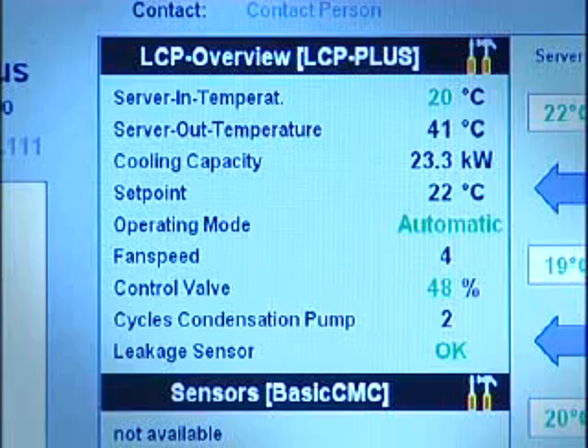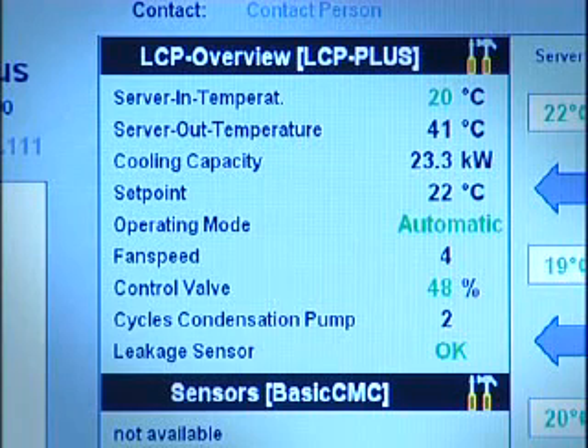Because of the large cooling capacity of the LCP Plus, it can be shared across a number of enclosures, effectively providing 2 enclosures with up to 15 kilowatts per rack. This gives you a greater flexibility to use the LCP Plus wherever and whenever you need to. Cooling is only one part of the functionality of the LCP Plus. Remote monitoring and control is essential so you understand what's going on within your high-density enclosure, and also you can adjust any parameters to suit individual applications.